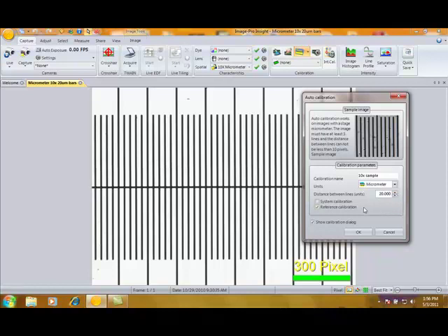And then I need to choose whether it's a system calibration or a reference calibration. If you're not familiar with this, a reference calibration is nothing more than all of the available calibrations that you've created. So if you have five objectives, you can create one for each objective. If you choose system calibration, that means the calibration that we're going to create now will become the active calibration if you have a camera set up through Image Pro Insight. So when you acquire images, that's the calibration that will be applied, the spatial calibration, to those images.